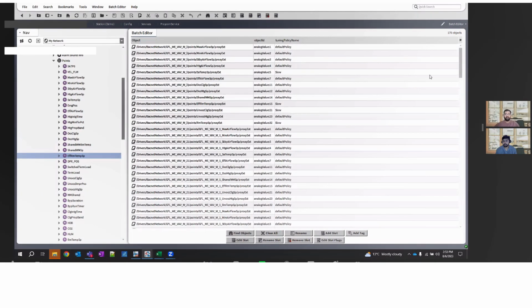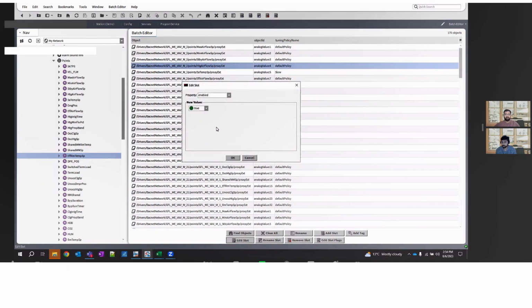So all the points are available, and you can see the tuning policy has been defined as slow in a few cases, which I did using the BACnet point manager view, or the default. Now I'll click on edit slot and tuning policy name. The trick here is it doesn't display the drop down values, so you'll have to manually type them.